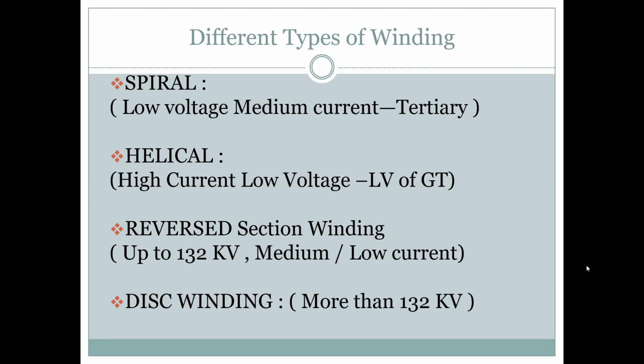So many of these things are there. Every state electricity board has different specifications, so all the transformer manufacturers cannot standardize anything. It depends on what is coming to them. And the KVA rating of the transformer is not decided by the transformer manufacturers. You only know your consumption of load, and that you have to decide. Your project, what the consumption is, what kind of load it is, inductive load, capacitive load, whether there are harmonics or not.